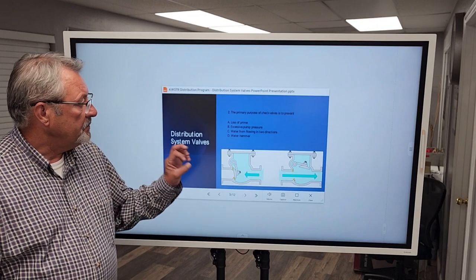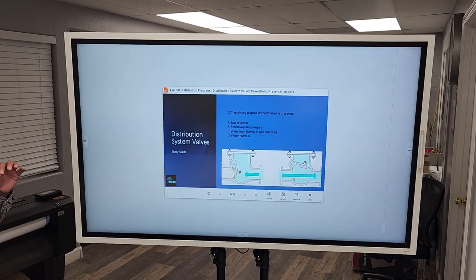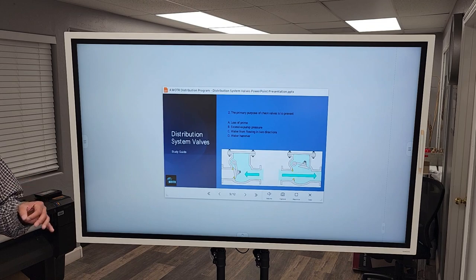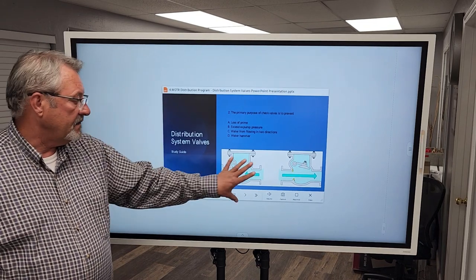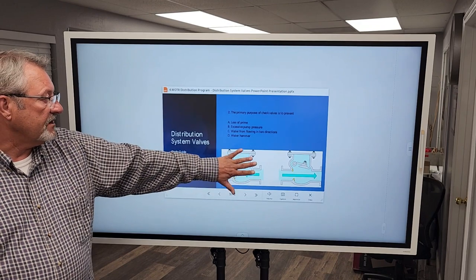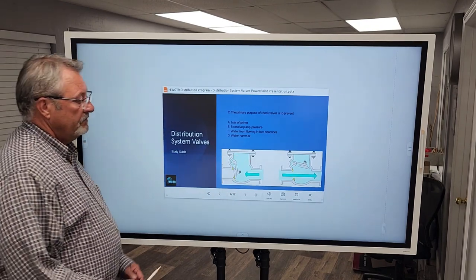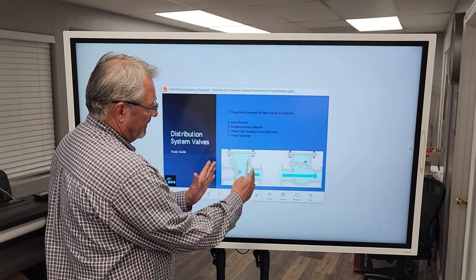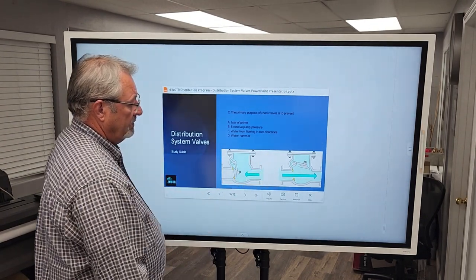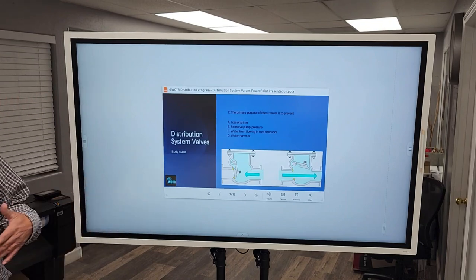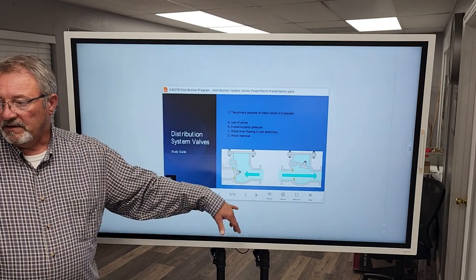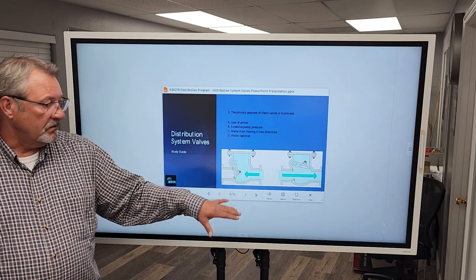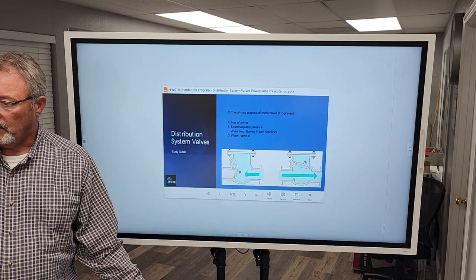I want you to keep something in mind when it comes to valves. They're named according to the closure element. So every valve has an element inside. And this is a check valve. We have double checks. You'll see a check valve that has two swing checks. It's kind of a backup, right? And then at the bottom of that will be a dump. It's an opening. So if those checks activate, it'll dump water.